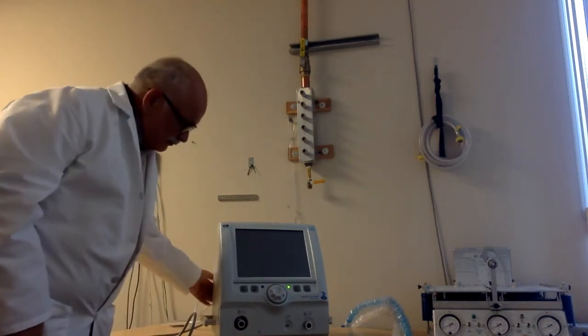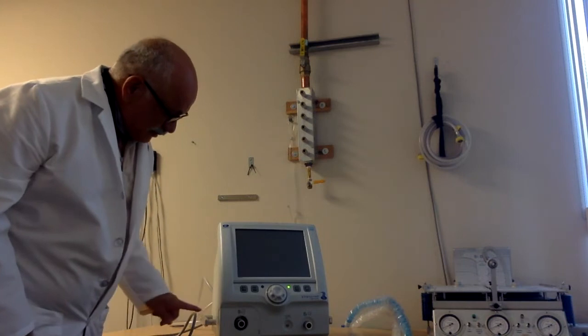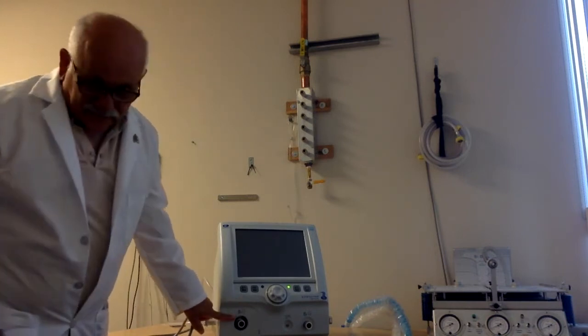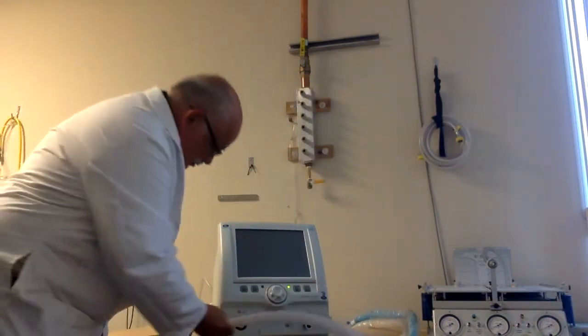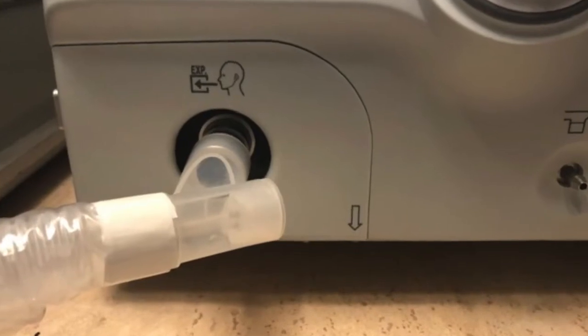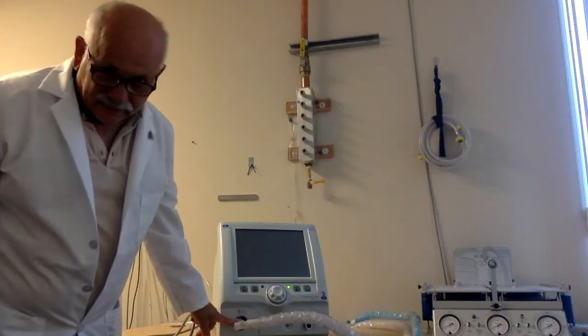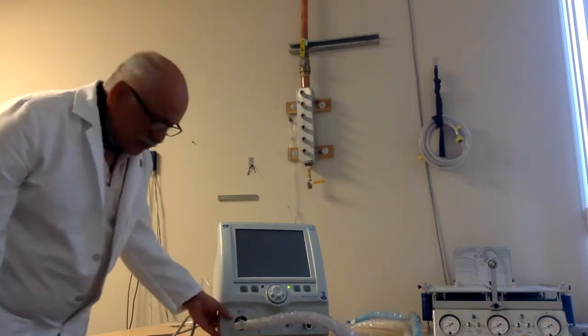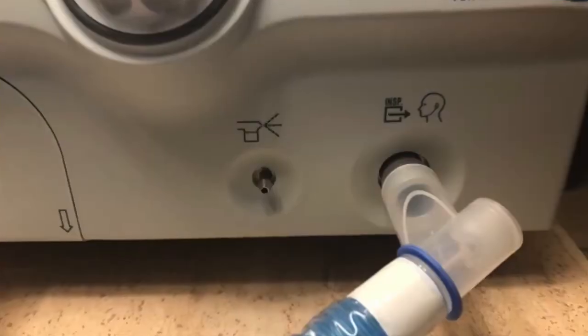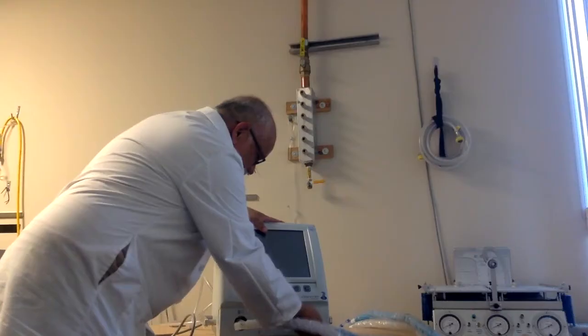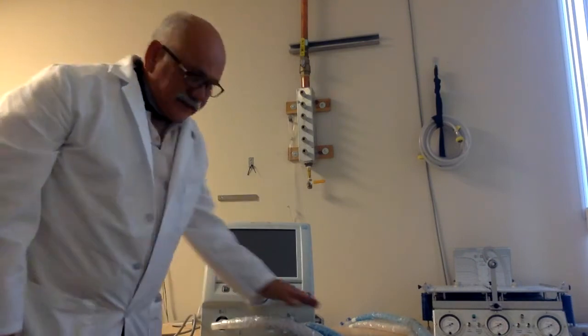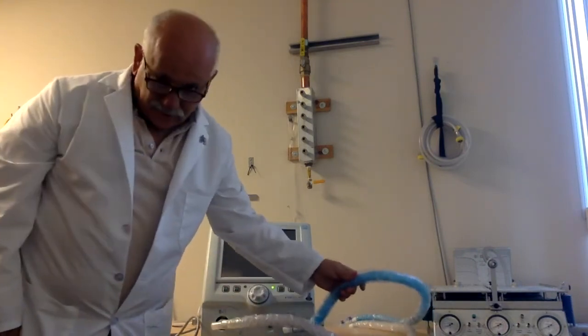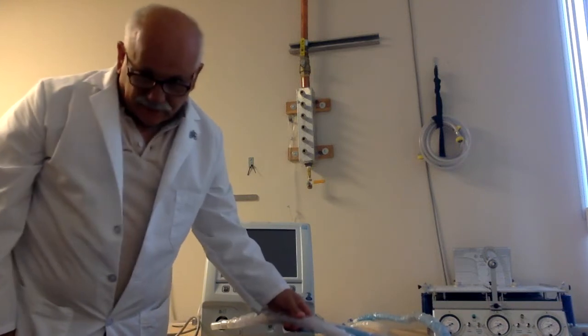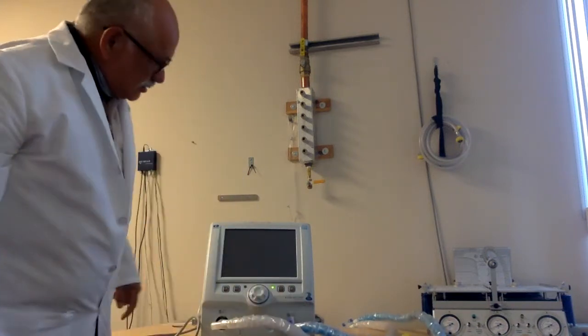Reaching behind here, I'll flip the switch, but before I do, I just want to point out, here we have an exhaled manifold. You would attach your exhaled circuit. You can put a filter there, generally recommended, especially in COVID days. This block is heated. And you have your inspiratory manifold. I'll be attaching the inspiratory line. Generally speaking, circuits are blue on the inspiratory side and white on the expiratory side. But that's not a standard, it's just a general statement.